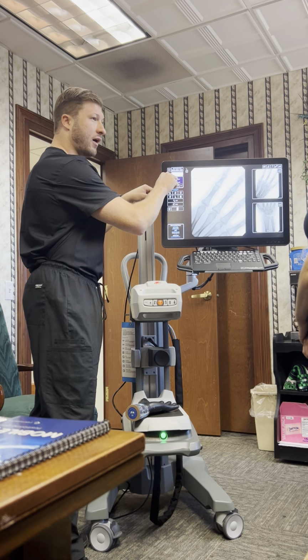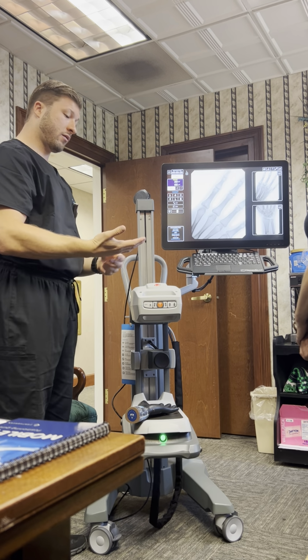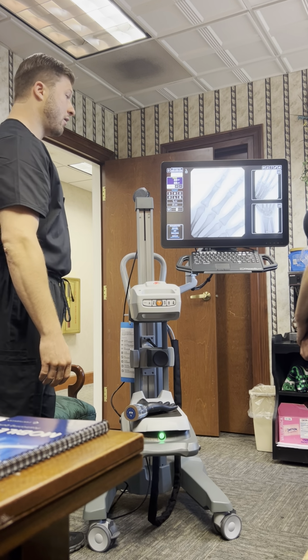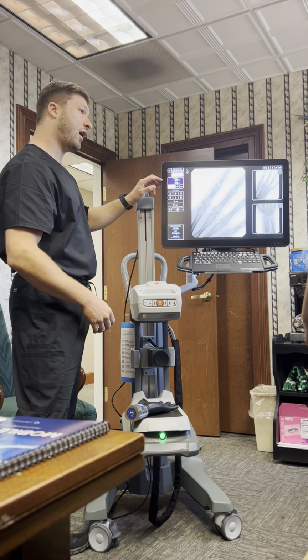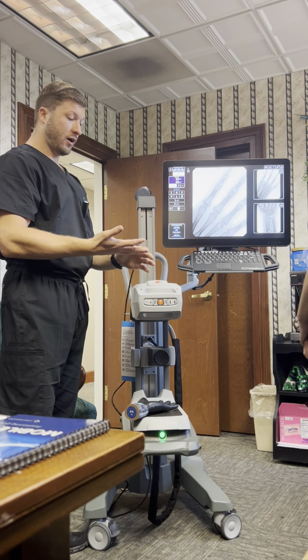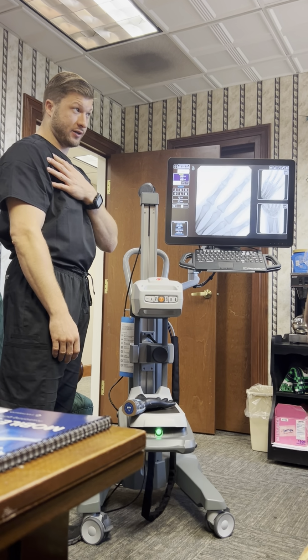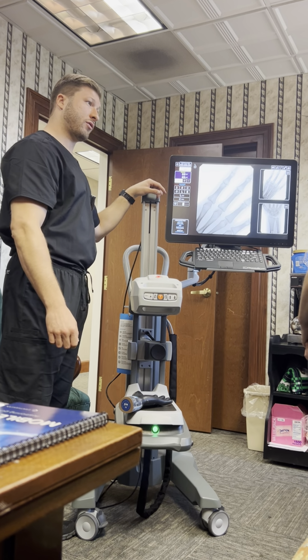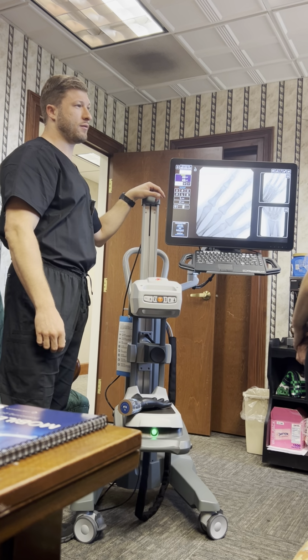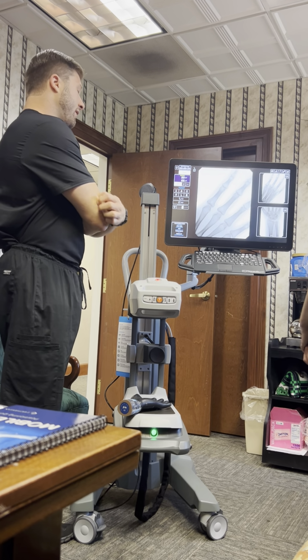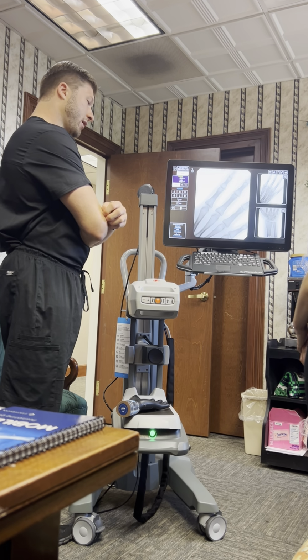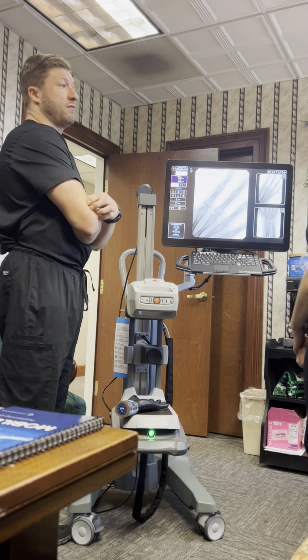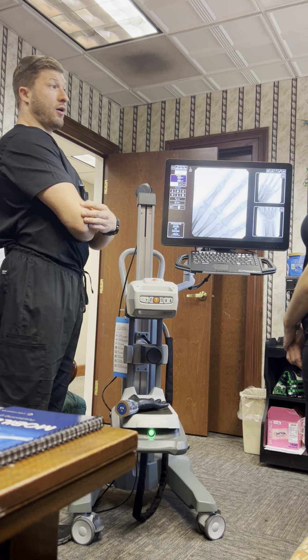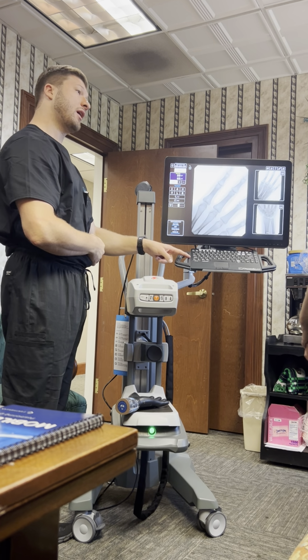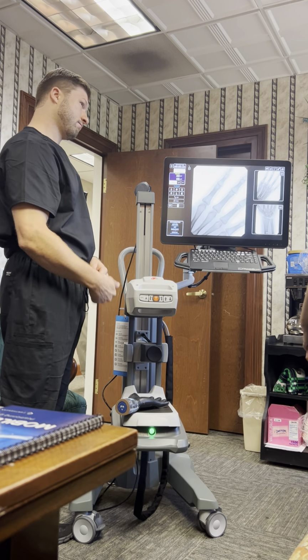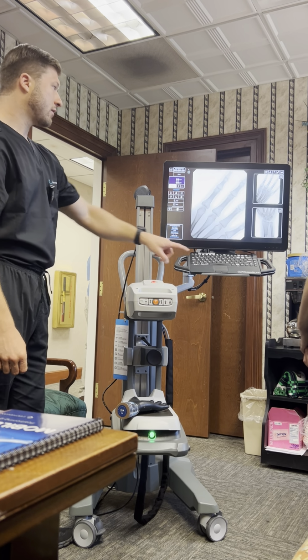But if we're sitting at 55 kVs and we don't hit boost, and we're going from a distal finger to a shoulder patient maybe, I recommend hitting the boost button, because it's going to go from 55, and we're telling the device we're going from a less dense piece of anatomy to a very dense piece of anatomy. So hit boost, hold that foot pedal down for 3 seconds, and it'll get up to the kVs it needs to get up to. Other than that, the boost button is just a good function to use for any dense, large individuals. If I see a big individual walk in, an offensive lineman, a bariatric patient, I immediately hit boost, especially if it's a shoulder or a knee. Okay. Yep. So, other than that, I'm just going to turn boost off.